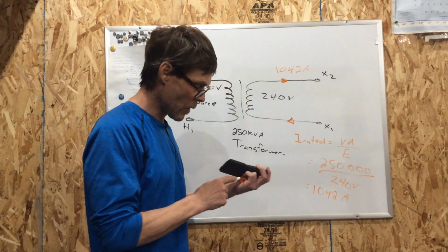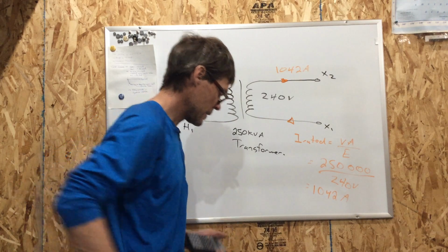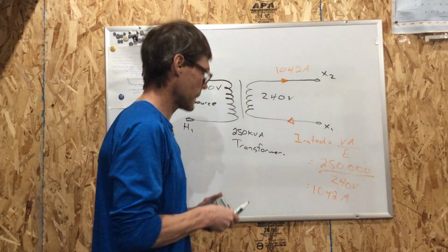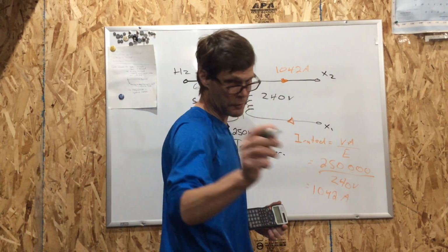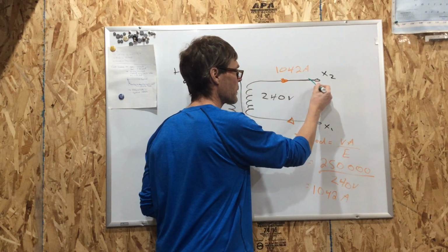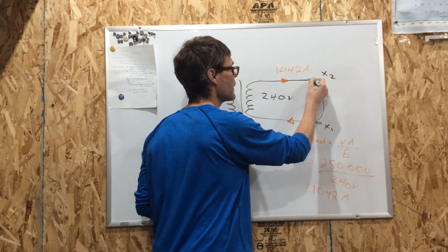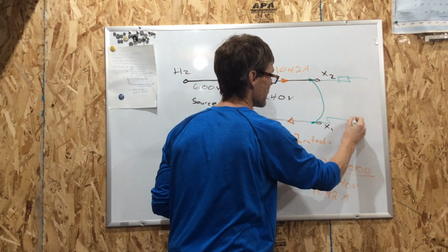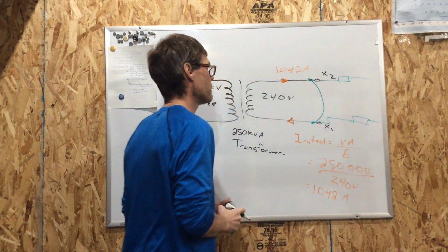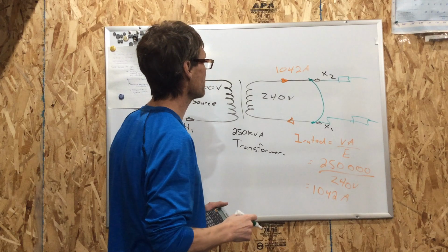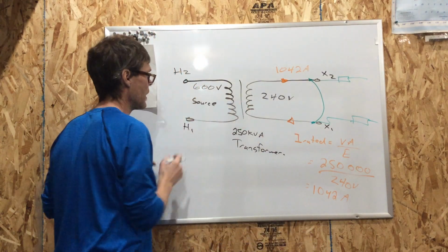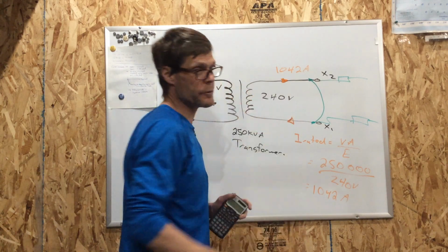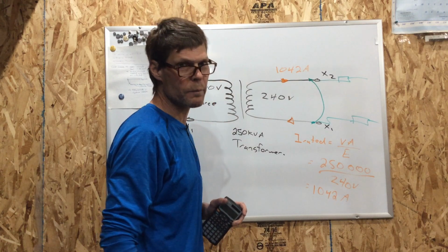All right. Now, what is short circuit? Short circuit, what we're going to say is that we have had a line-to-line fault on our secondary. So picture this. Don't go do it. Picture this, that something metal has fallen across here. And let's just picture for a moment that our secondary fuses are downstream, pardon me. So now we're relying on high voltage fuses. But right now, we've released an incredible amount of energy. So what's the only thing holding back current right now?